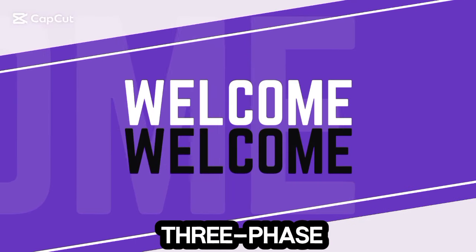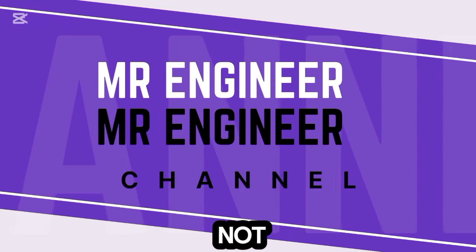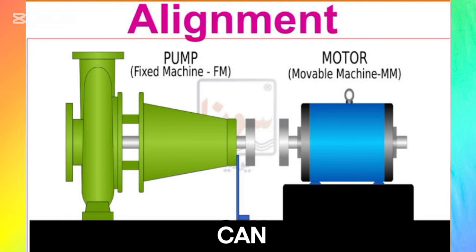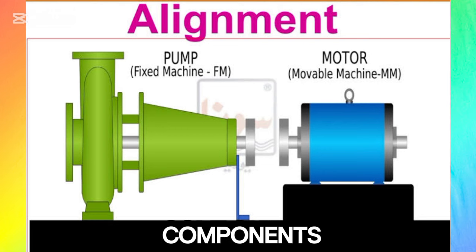Misalignment between a three-phase motor and a pump occurs when the motor's shaft and the pump's shaft are not properly aligned. Misalignment can cause a variety of issues, including vibration, noise, excessive wear, and potential failure of components. It typically occurs in three forms.